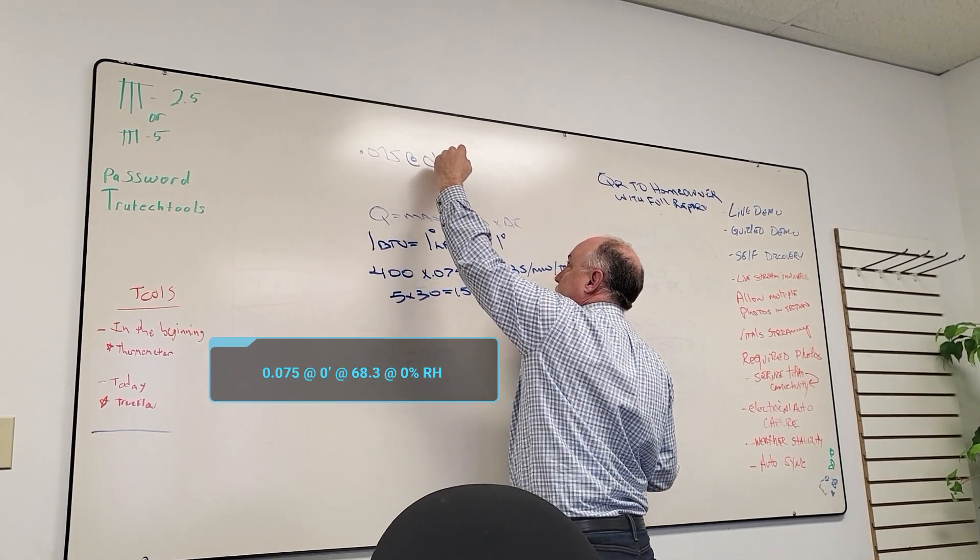When we talk about standard air, you guys have all heard of standard air. This 0.075 is under what conditions? Sea level, at what temperature? 68.3. What relative humidity? Zero. Zero percent relative humidity. Unless maybe you're in Phoenix six days a year, you have to be in a very arid climate. Just a little factoid: in 1924, the Heating and Ventilating Society actually revised their definition of standard air to 70 degrees at 50 percent relative humidity. But this is considered standard air. And the difference, by the way, is less than two percent.